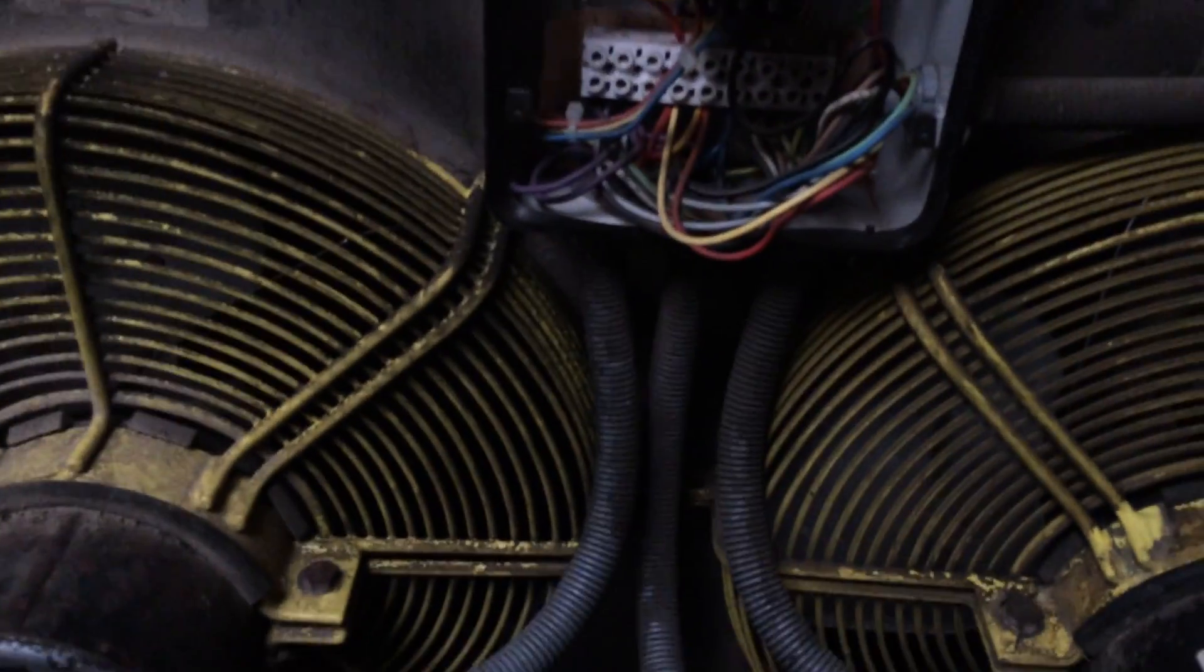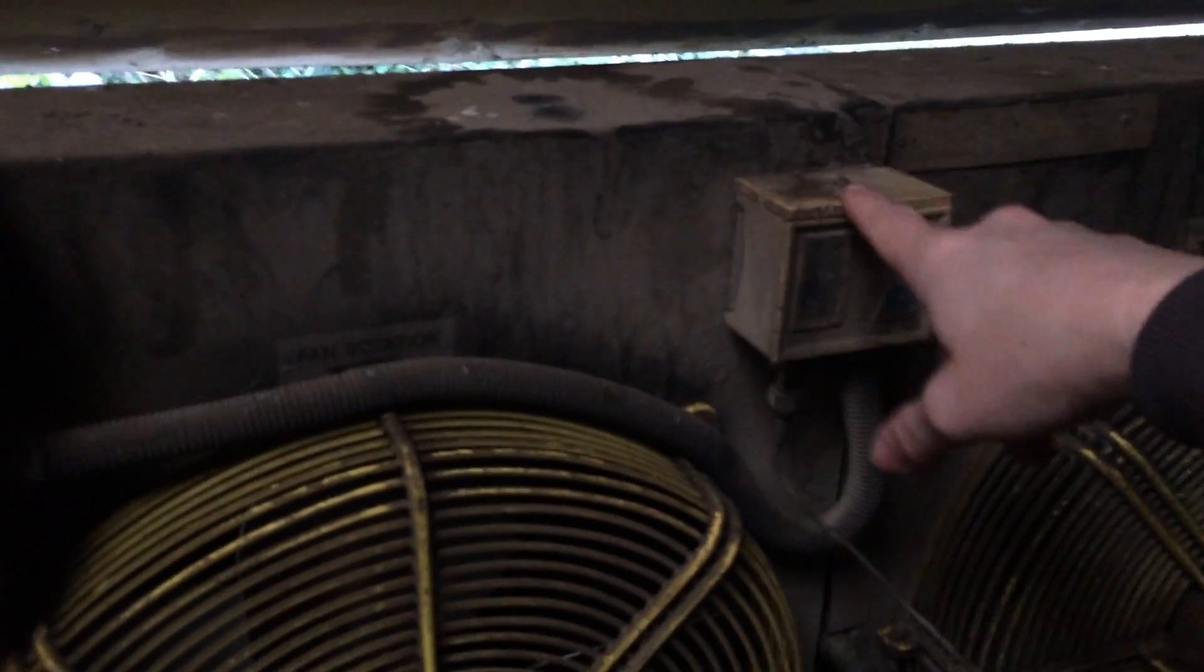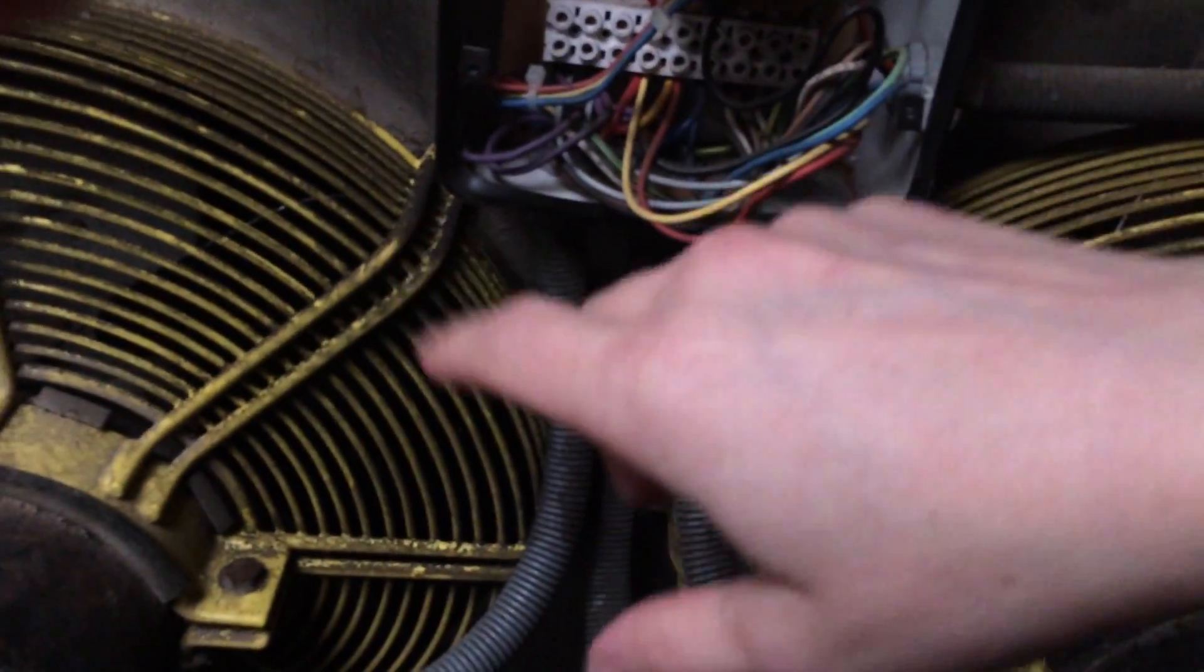Anyway we've fired it up. The thing fires up. The second fan is off another pressure switch. You can hear the contactor click in but the fan doesn't run.